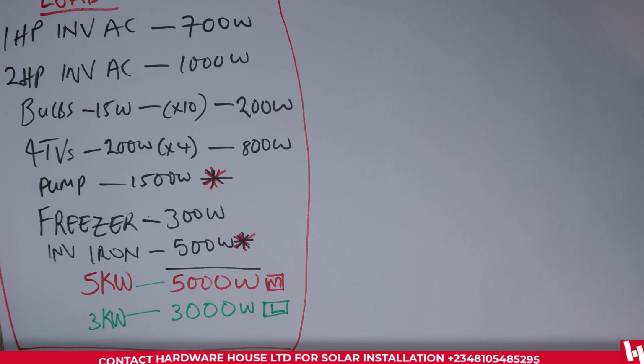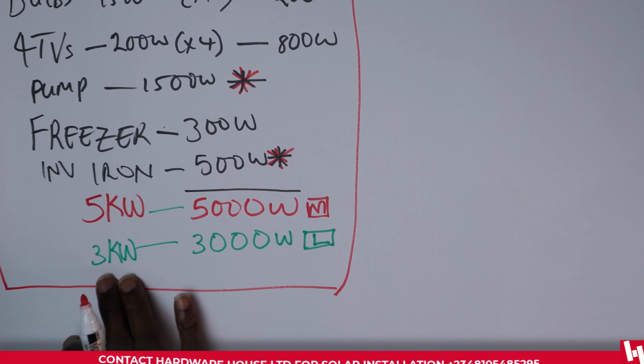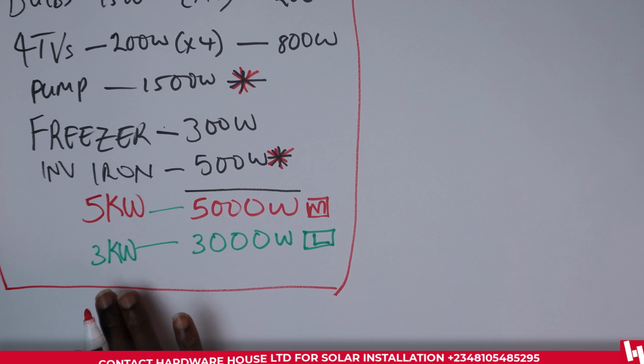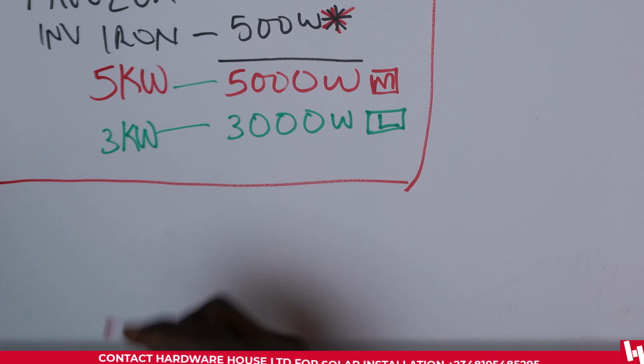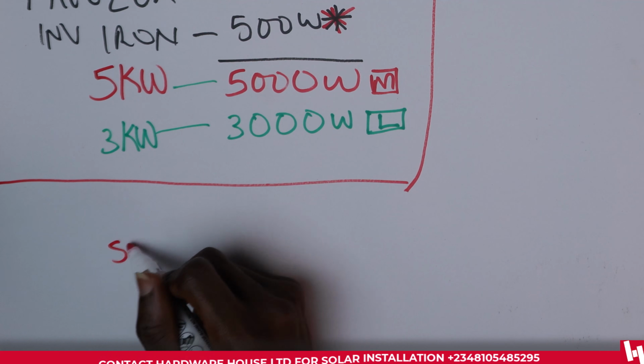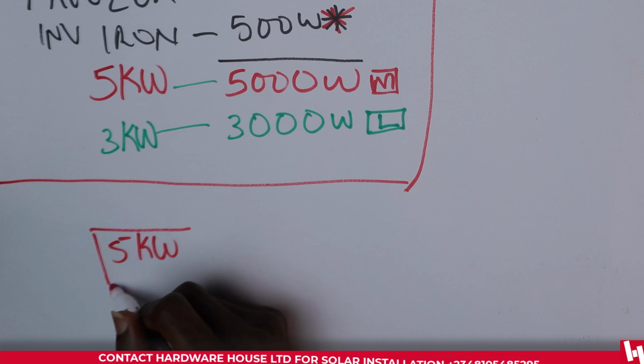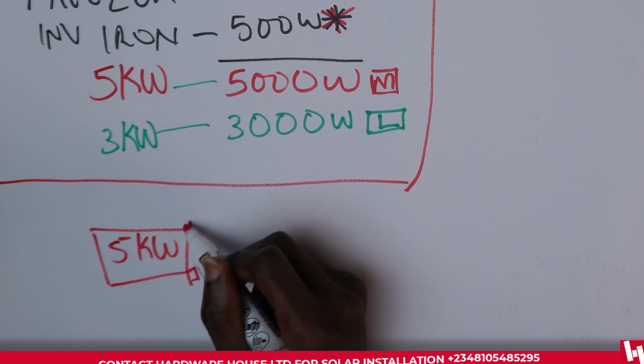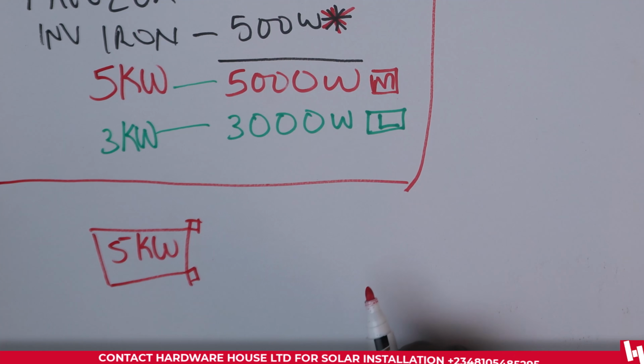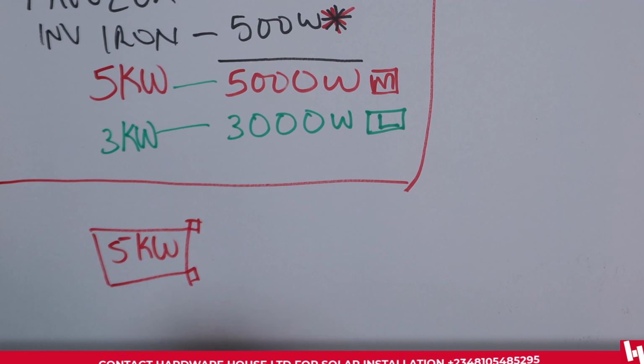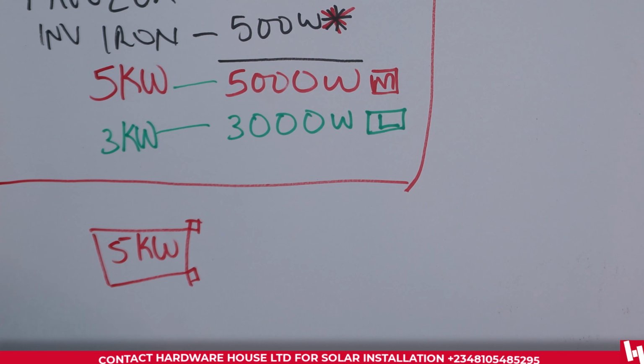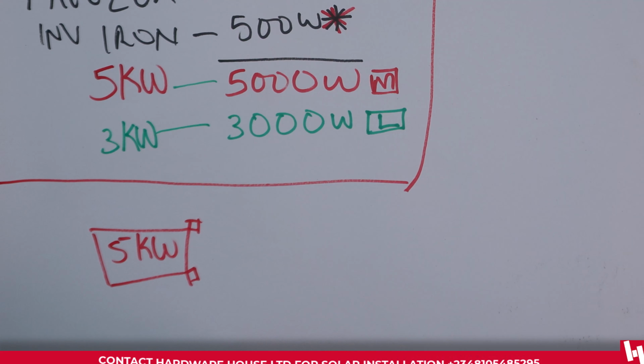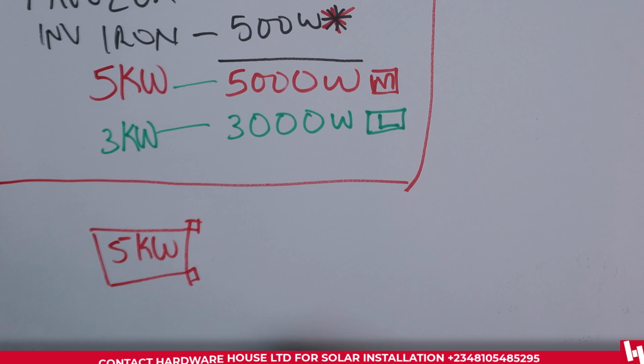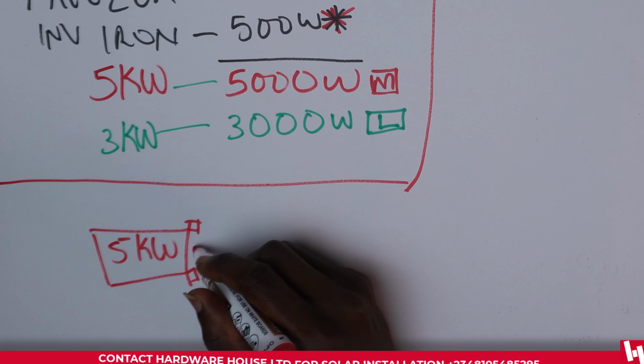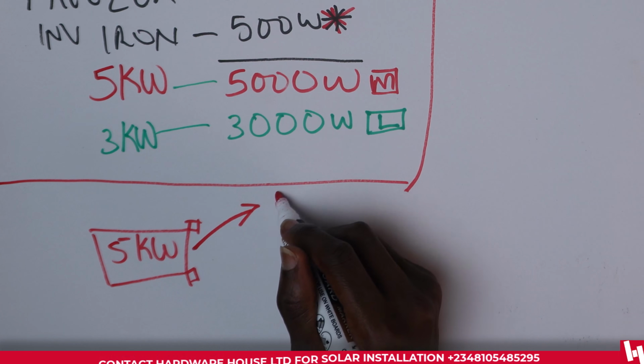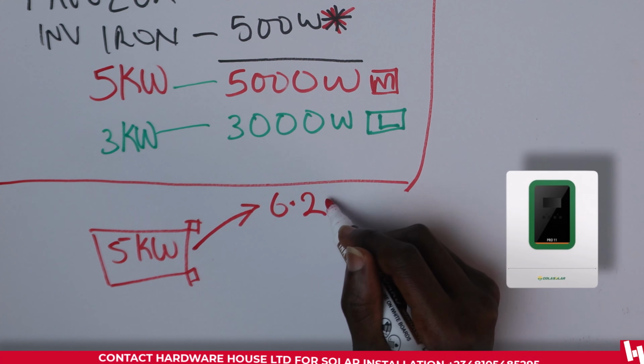So we have a total load. We're leaving this because we want to give as much allowance as possible so our system can overperform beyond expectations. We're taking 5 kilowatts as the load, assuming both pumping machine and pressing iron stay on alongside a 2 horsepower and a 1 horsepower inverter AC continuously run. We would have 5 kilowatts maximum.